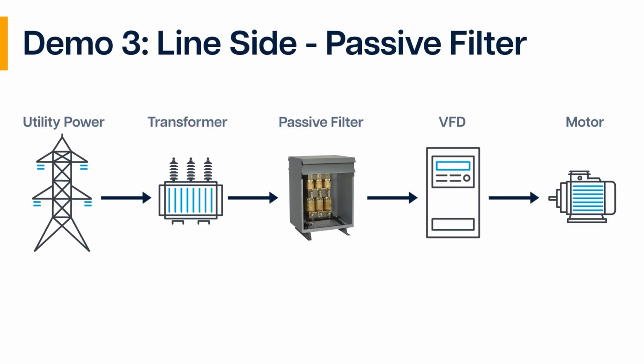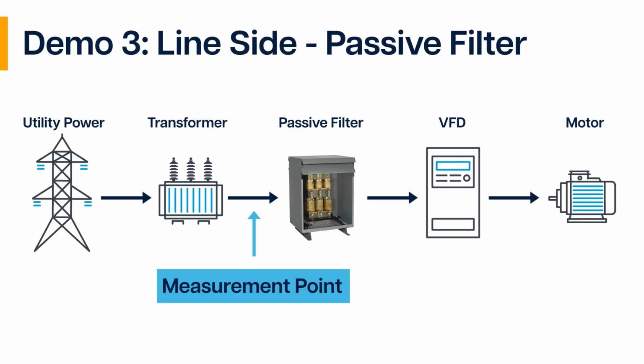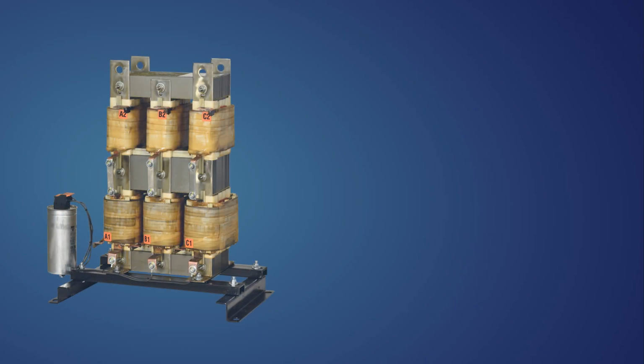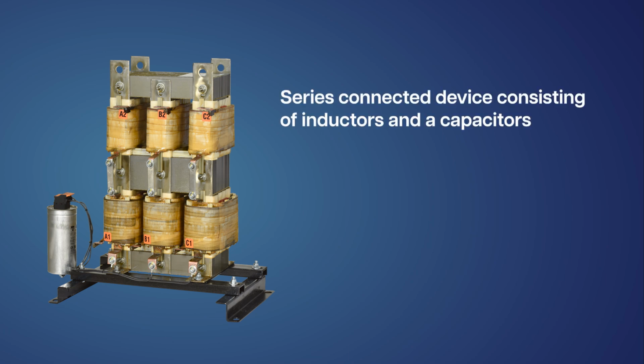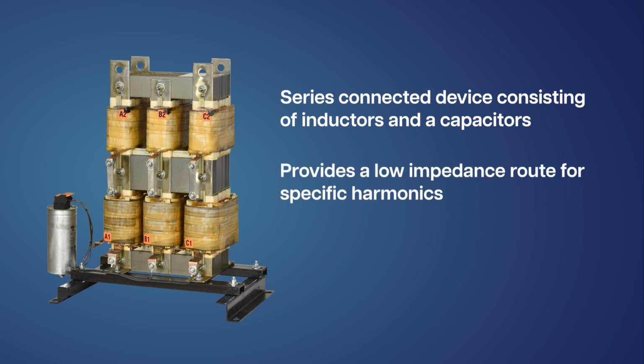For Demo 3, we introduce a passive harmonic filter into the circuit. A passive harmonic filter is a series-connected device consisting of inductors and capacitors configured in such a way to create a tuned circuit. This tuning process enables the filter to provide a low impedance route for specific harmonics, effectively channeling them into the filter and away from the broader power system.